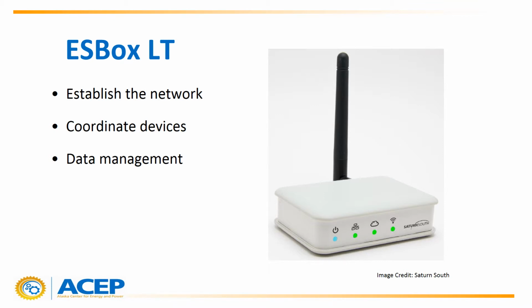The ESBox provides the link between the energy services company and the meters by establishing the Zigbee network for the demand management system. Understanding how this device locates meters and retrieves and stores data is essential to profiling the ESBox. Meters must request to join the network, and the ESBox acts to identify and authorize each device. The ESBox is used to manage and organize the network. Commands to the meters are deconstructed by the ESBox, and results are then stored in the ESBox until either requested by the user directly or delivered to a secondary database set up by the user.